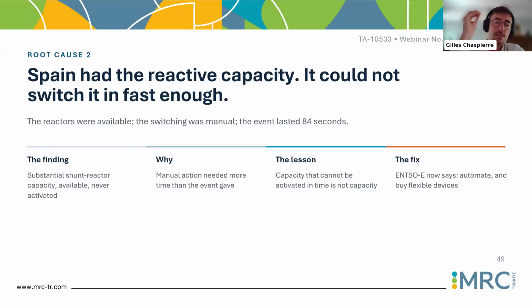But because, as discussed, if you want to know the numbers, it's simple. They have 4 GVAr of shunt reactors, and 2.7 GVAr were not used, were out of service during the blackout. Imagine if you had been able to connect everything, I'm not sure we would have seen such high voltage, and probably the blackout could have been avoided.